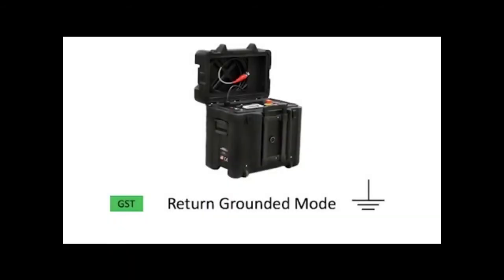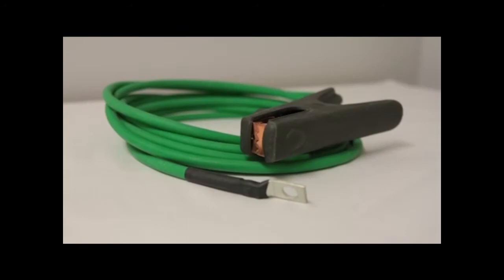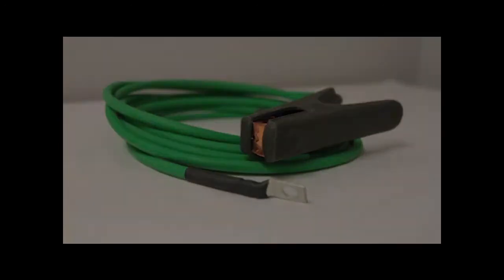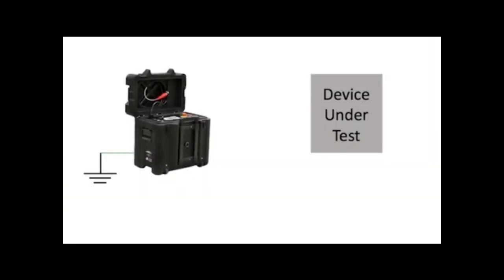First, we will review return grounded mode. To begin, make sure the DC HiPOT is grounded using the grounded or earth cable that comes from the DC HiPOT. For safety reasons, this ground cable should be the first lead to be connected and the last to be disconnected.